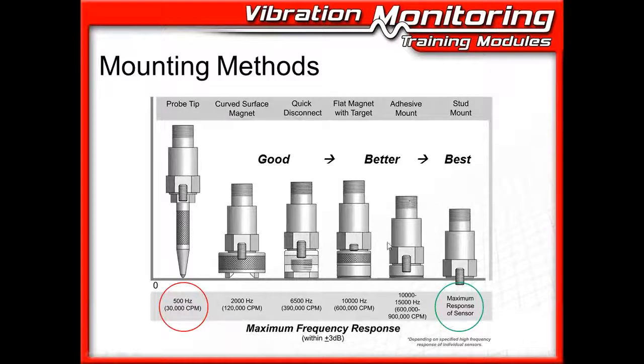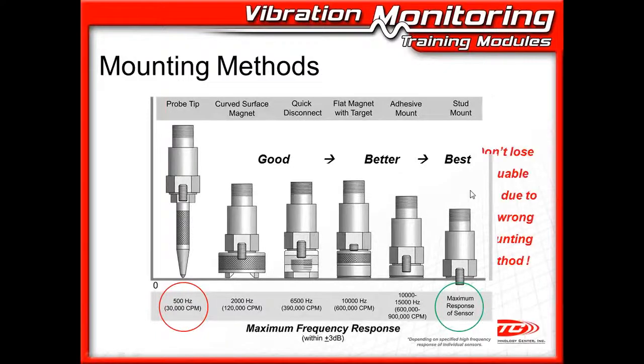Here's our epoxy pads. When you're doing epoxy mounting, cleanliness is number one. No paint, no rust, no oil. You've got to have a clean, flat, dry surface, and that'll help that epoxy really take hold and stick. And then the very, very best you can do is stud mounted. And like I said, you've got a good, reliable connection here, as well as nothing between the sensor and the machine. So you get the maximum response of the sensor if you do this.